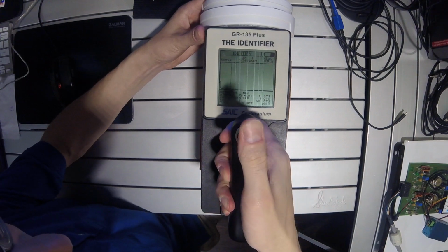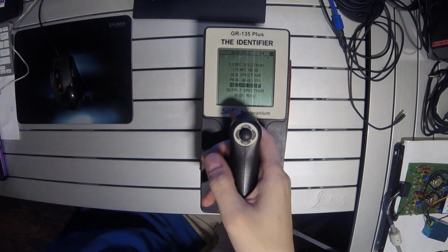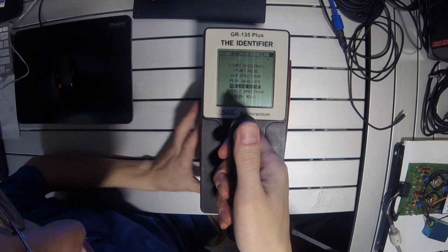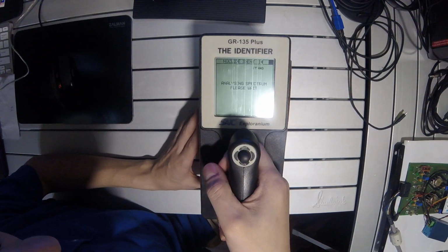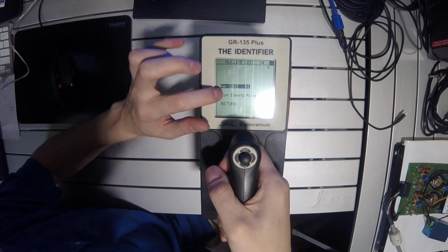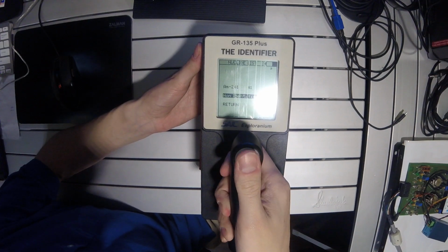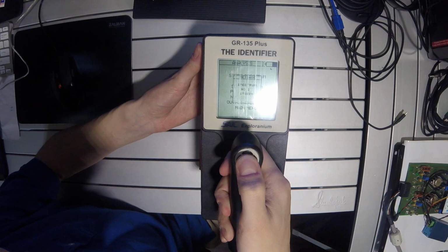And it's a little past 30 seconds, so I'm going to stop the acquisition and go to nuclide identify. And in fact, it does have it, americium-241. So it can identify something as weak as a smoke detector source. So let's return to that menu and go to store spectrum. So spectrum number 2 stored.